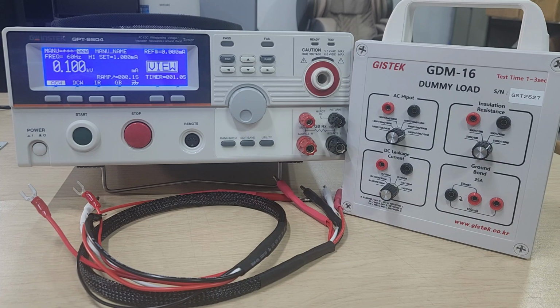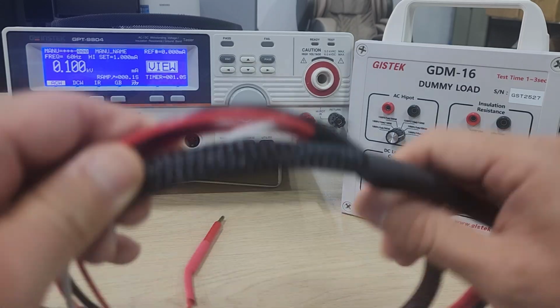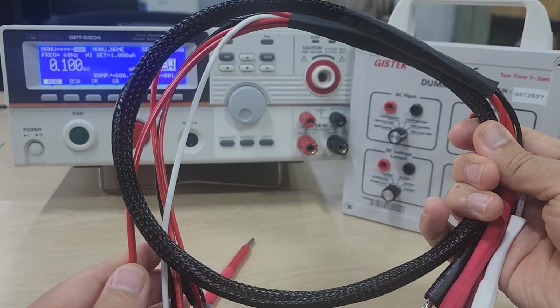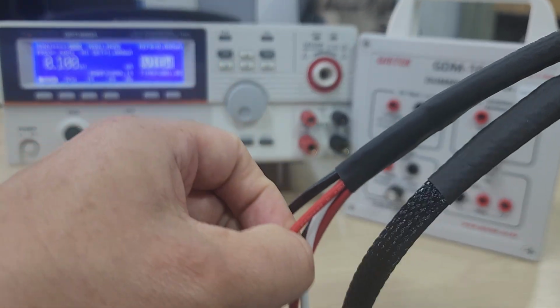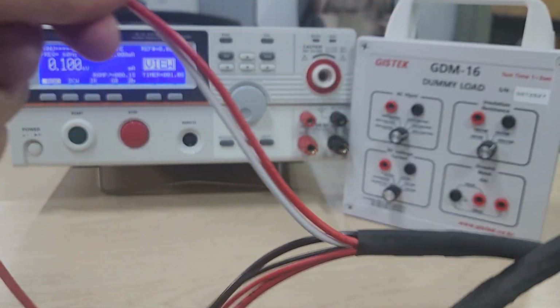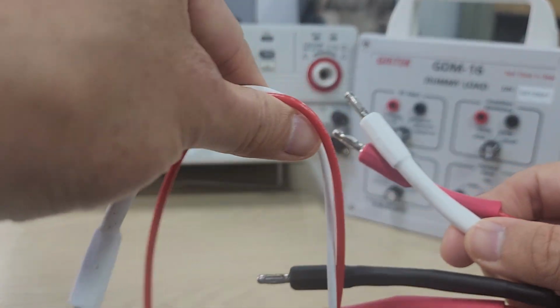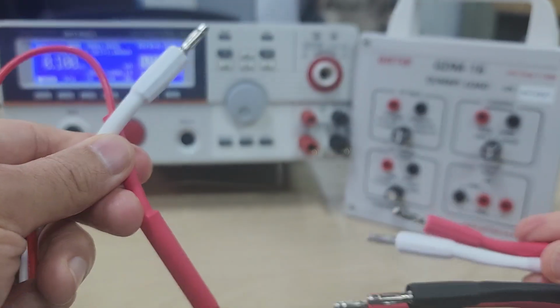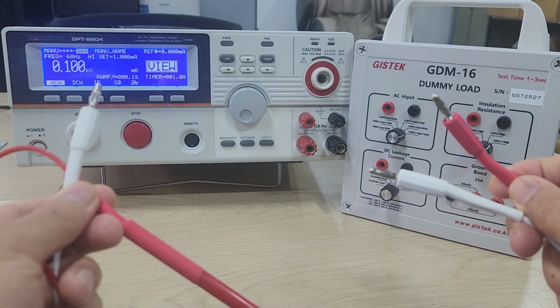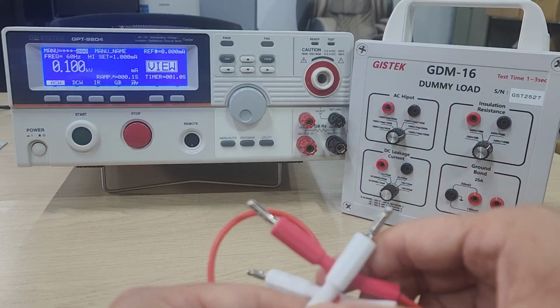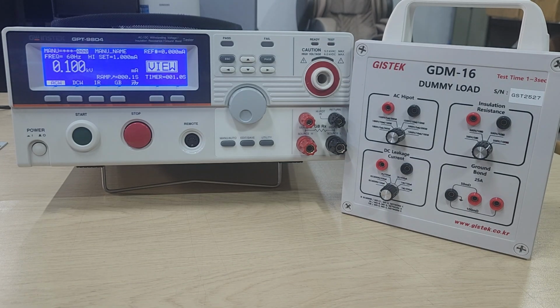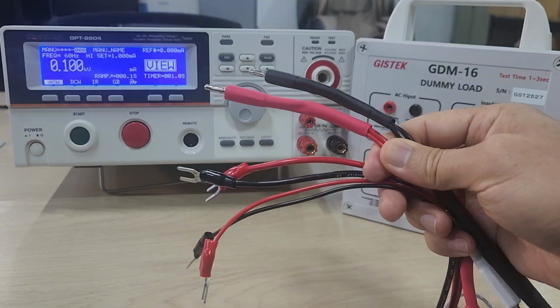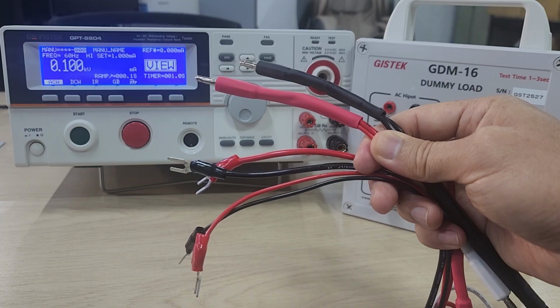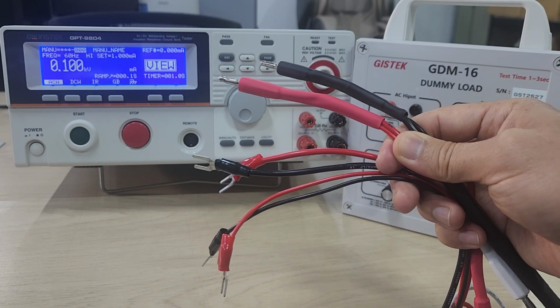Next, we will introduce how to check an electrical safety standard tester with a dummy load. I will explain the dummy load connection cable. This soft silicone cable, this red cable and white cable, these two and these two, is used for AC withstanding voltage, DC insulation resistance, and DC leakage current testing. And this 4-strand cable made of slightly stiff general cable is only for grounding resistance testing.